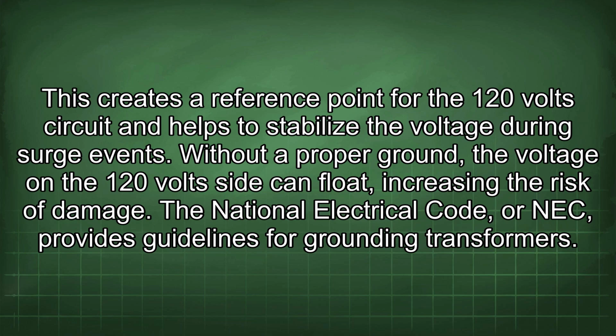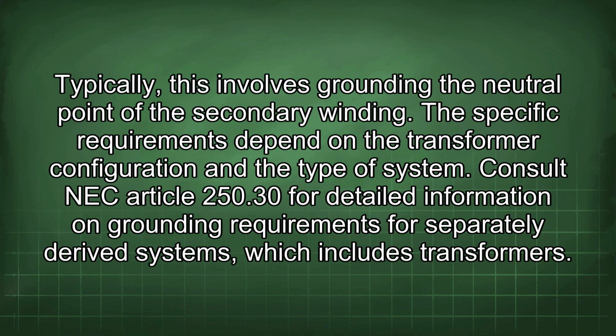The National Electrical Code, or NEC, provides guidelines for grounding transformers. Typically, this involves grounding the neutral point of the secondary winding. The specific requirements depend on the transformer configuration and the type of system. Consult NEC Article 250.30 for detailed information on grounding requirements for separately derived systems, which includes transformers.